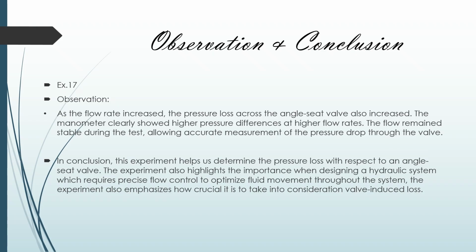Exercise 17. Observation. As the flow rate increased, the pressure loss across the angle seat valve also increased. The manometer clearly showed higher pressure differences at higher flow rates. The flow remained stable during the test, allowing accurate measurement of the pressure drop through the valve.